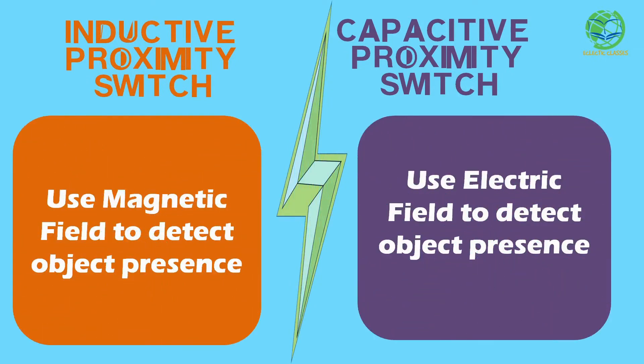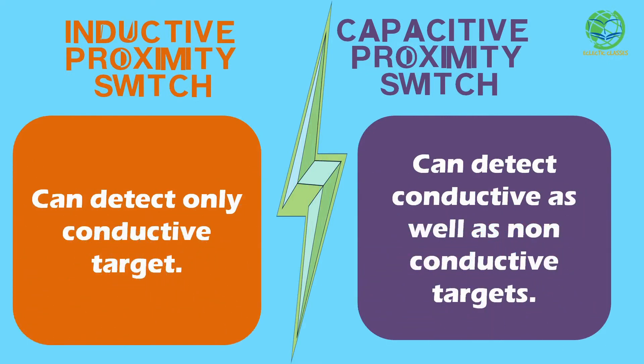Inductive sensors use a magnetic field to detect objects, while capacitive sensors use an electric field to detect the presence of any object. Inductive sensors can sense only conductive targets, so our choice gets limited to metals, while capacitive sensors can sense metals as well as non-metals.